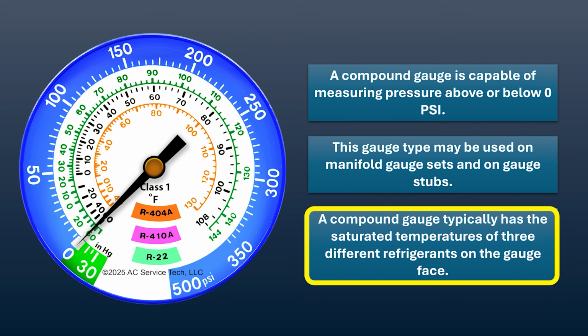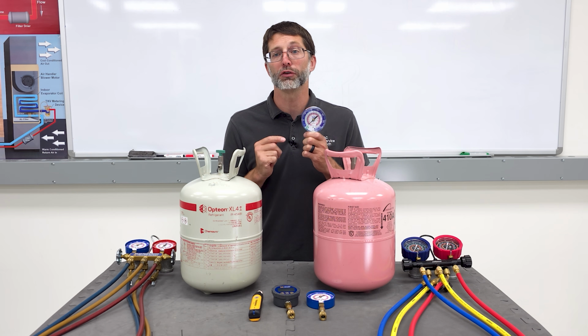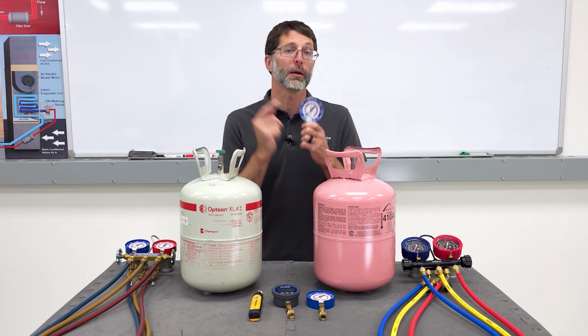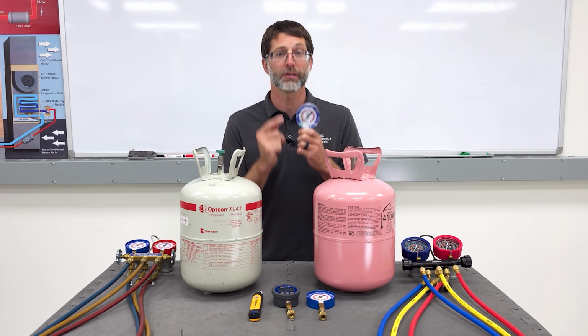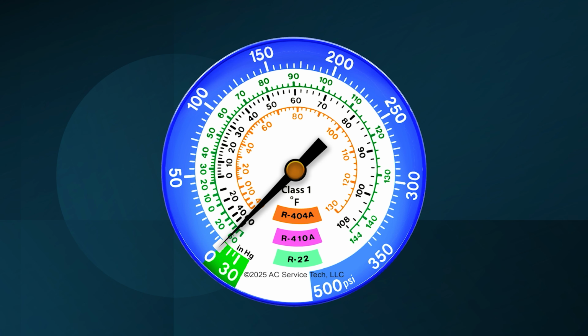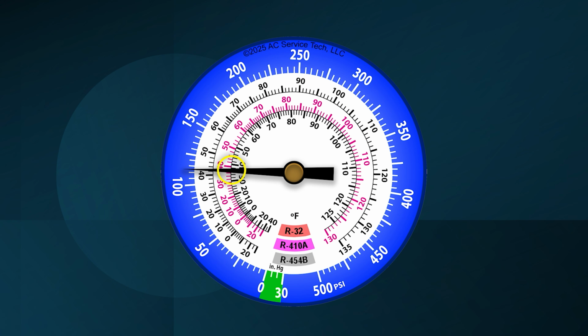A compound gauge typically has saturated temperatures of 3 different refrigerants on the gauge face. Manufacturers make compound gauge faces with different combinations of refrigerant saturated temperatures. Figure 4-25 shows a blue low side gauge that has a saturated temperature for R22, R410A, and R404A, while figure 4-26 shows a saturated temperature of R454B, R32, and also R410A.